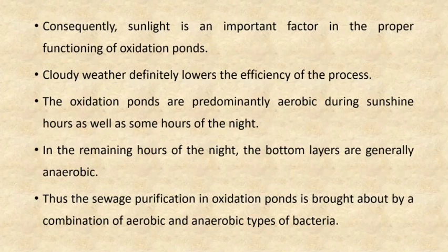Cloudy weather definitely lowers the efficiency of the process. These oxidation ponds are predominantly aerobic during sunshine hours, as well as some hours at night, and in the remaining hours of the night, the bottom layers are generally anaerobic. So here is a combination of aerobic and anaerobic types of bacteria.